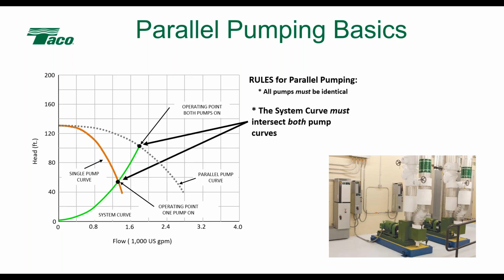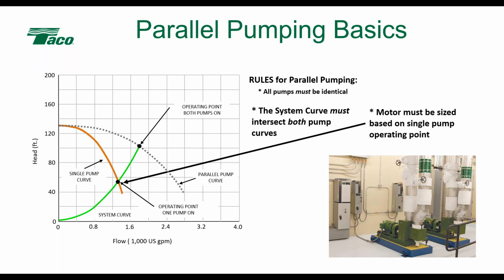It's also critical that in a parallel set where I've only got 2 pumps, the system curve intersects both pumps' curves. When I move into 3 and 4 pumps, I have to understand what my minimum is going to be to know how many pumps have to cross the system curve. So keep in mind that the motor is sized for that single pump operating point, so we don't get into an overload condition.